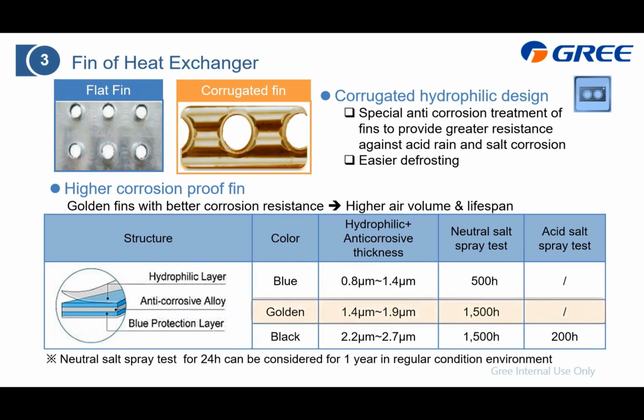So for the UMAX, the outdoor unit, we apply the golden fin. It already passed the 1,500 hours of the neutral salt spray test. And for this one, it is 24 hours. For it, it can be considered as 1 year in regular condition environment, which means for this one, it can last for a long time. And if you have a higher anti-corrosion level, you can also choose this black color. It can additionally pass 200 hours of the acid salt spray test. And also for detail, you need to contact your Gree salesman for detail.